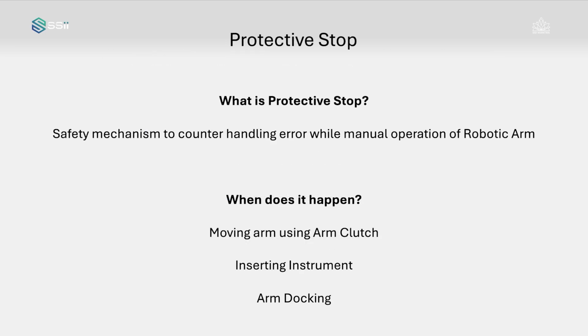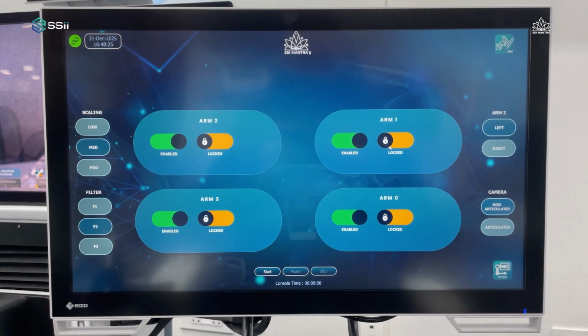Protective stop is a safety mechanism intended to address unintentional handling deviations by the bedside team during manual arm operation. Protective stops may occur while moving the arm using the arm clutch, while inserting the instrument, when the arm is being docked, or during other manual arm operations. Only the arm being operated is affected with protective stop. Rest of the system remains unaffected. Indication: automatic disabling of the affected arm.